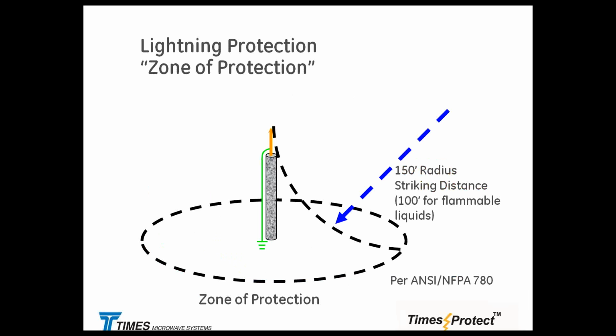And there was a question from someone basically, well, if I have the lightning diverter right here, Ben Franklin rod, sitting on the top of the tower, do I have to have that green wire coming all the way down? I've been fighting with that whole thing for almost, I mean, for as long as I remember. If you take a look at the 250 MCM insulated wire going to the ring ground around the tower and so on, and if you take a look at the massive leg or the massive monopole being right next to it, you know, that wire doesn't do very much.